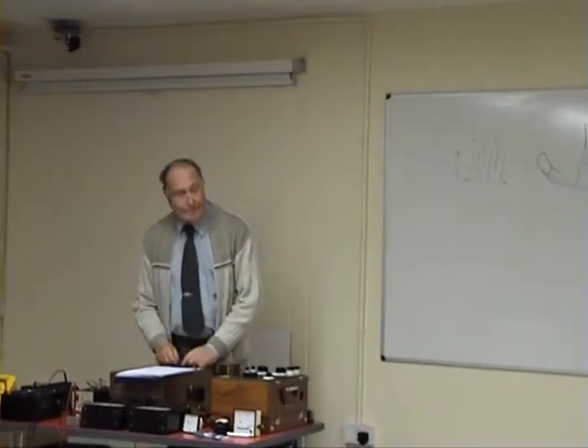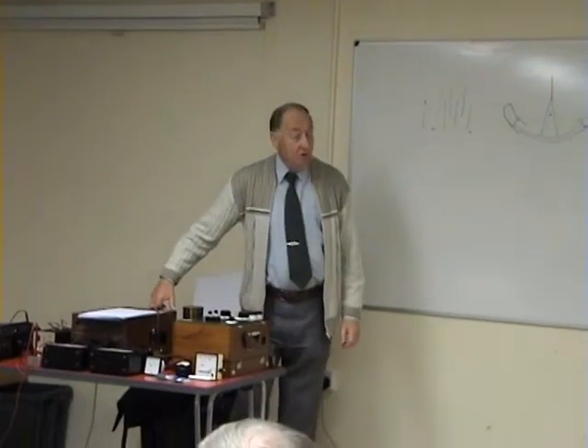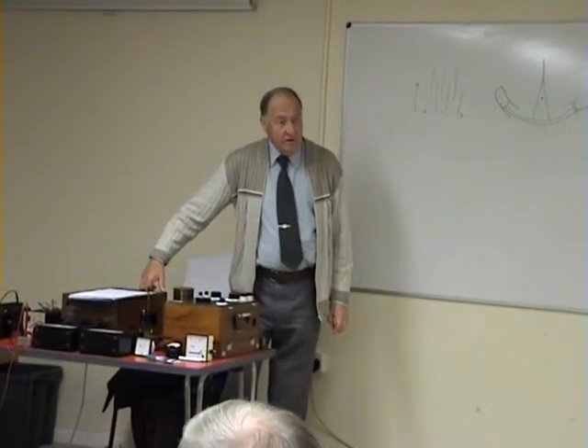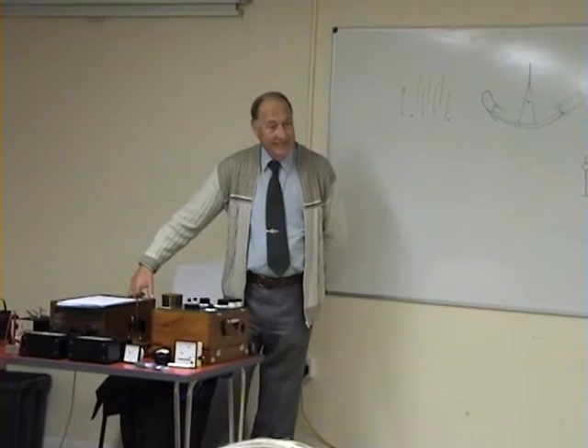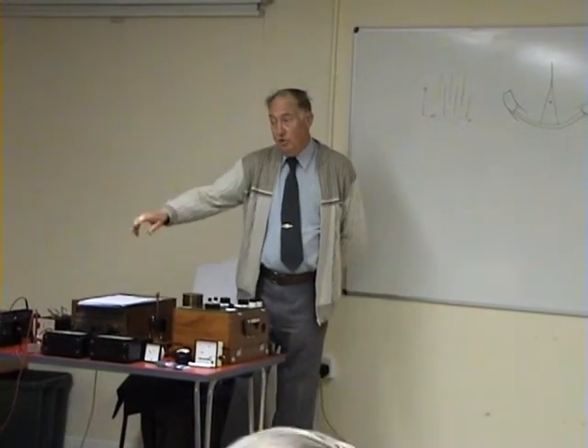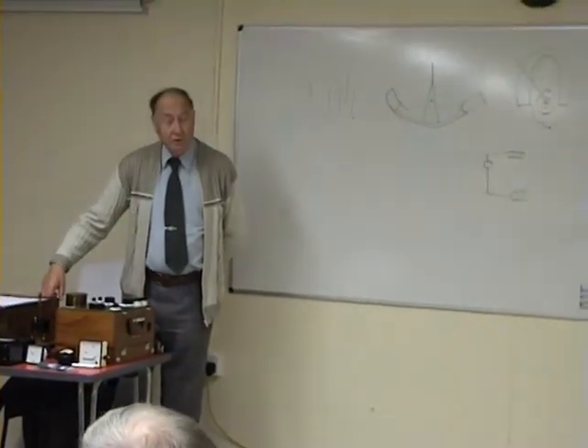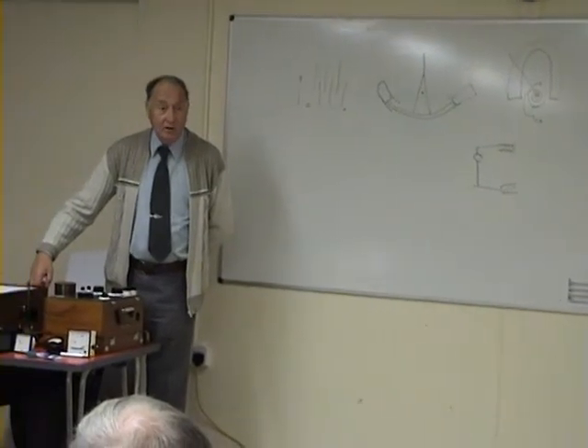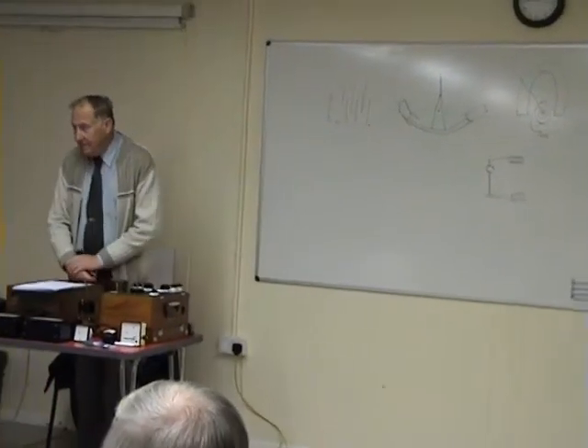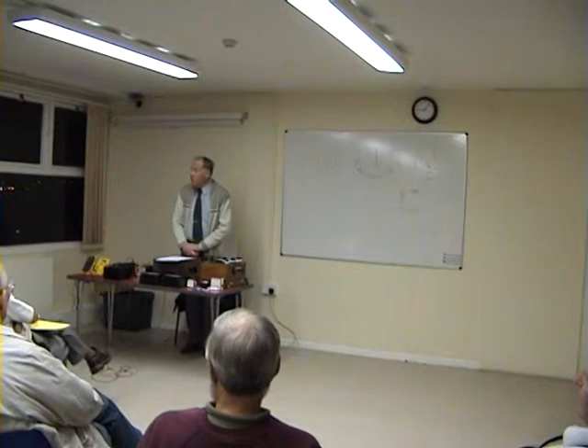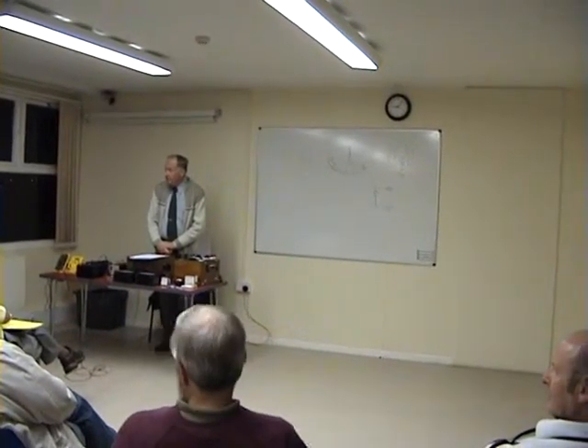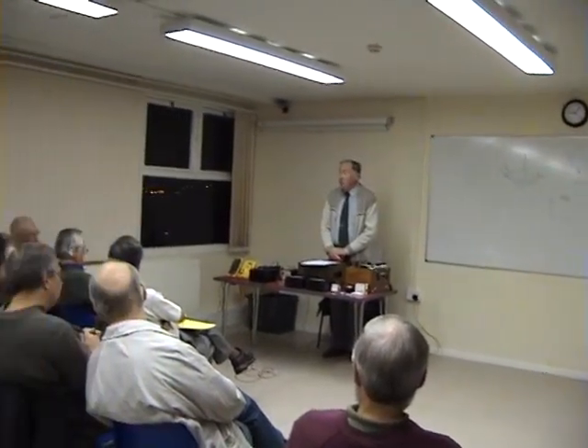Problems with the AVO ones - the small ones that come out, yes they do, always fall apart, as well as the verticals. Those Hirschmans rarely go wrong. They do go wrong, of course, but the AVOs tend to go wrong a lot. You had to recalibrate the meter because of those? I'm saying, did you have to recalibrate? No, but I have heard instances where the AVO ones get worn inside and make poor contact down the tubes.